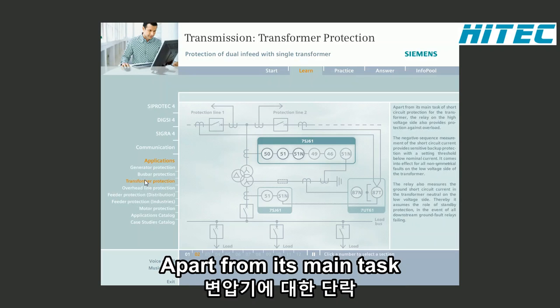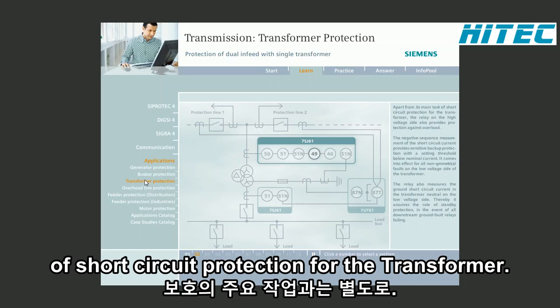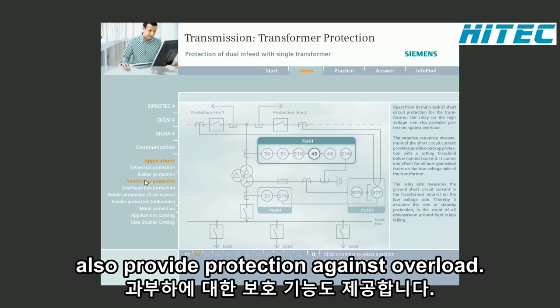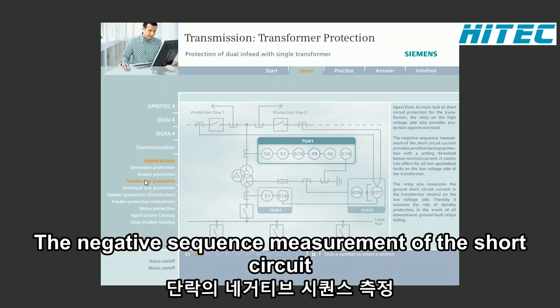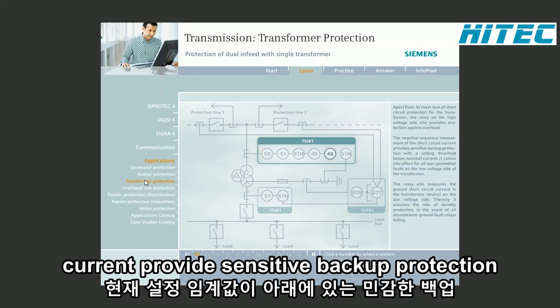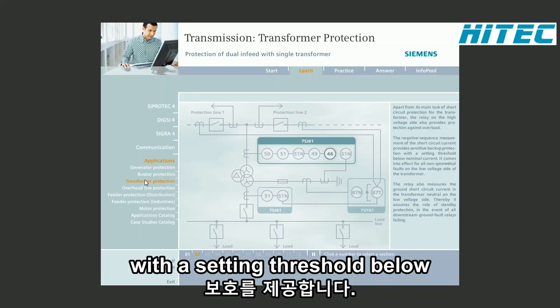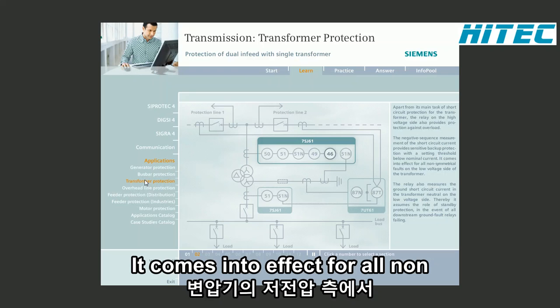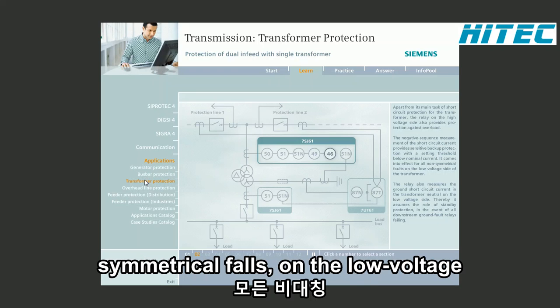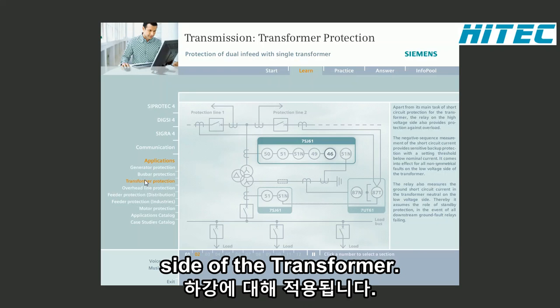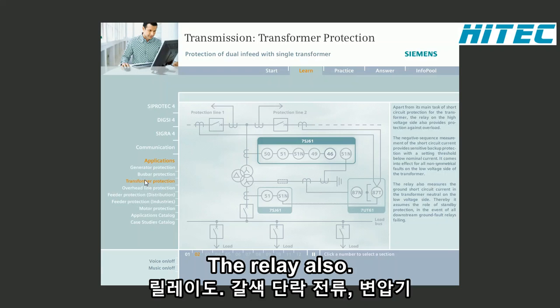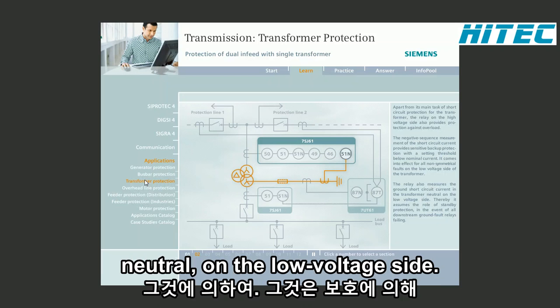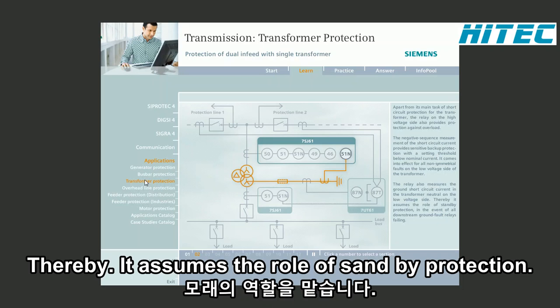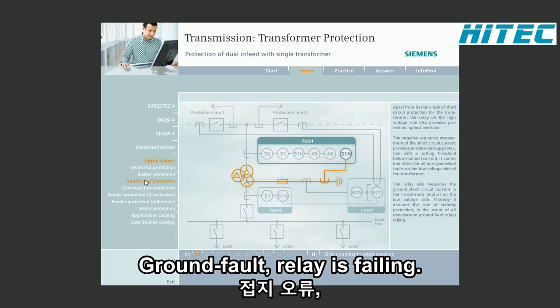Apart from its main task of short-circuit protection for the transformer, the relay on the high voltage side also provides protection against overload. The negative sequence measurement of the short-circuit current provides sensitive backup protection with a setting threshold below nominal current. It comes into effect for all non-symmetrical faults on the low voltage side of the transformer. The relay also measures the ground short-circuit current in the transformer neutral on the low voltage side. Thereby, it assumes the role of standby protection in the event of all downstream ground fault relays failing.